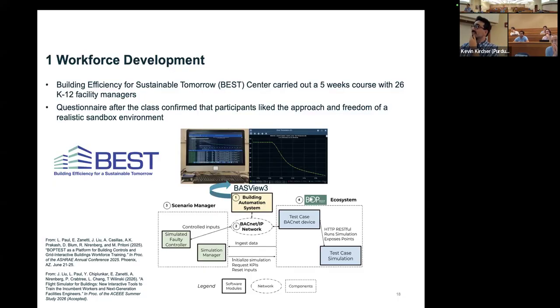And this is an example of the software architecture that was behind it. So at the core, there was BOPTEST with its backend interface, as I mentioned. And then the teacher would also create Python scripts that basically would override the controller and create these faulty scenarios. And those would be deployed to BASView3, which is an open source building automation system viewer. It's pretty bare-bones, but it's comparable to what you will find in the field. And there, as an example, there is a temperature trend showing what happens to the supply temperature after you close the damper.